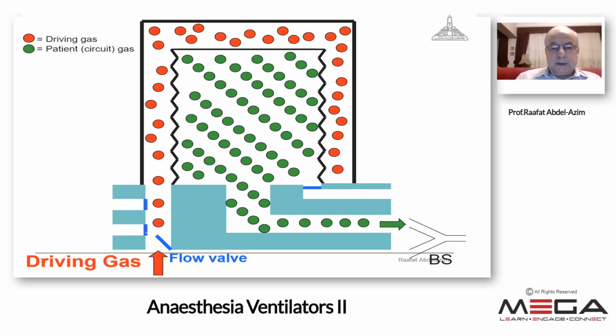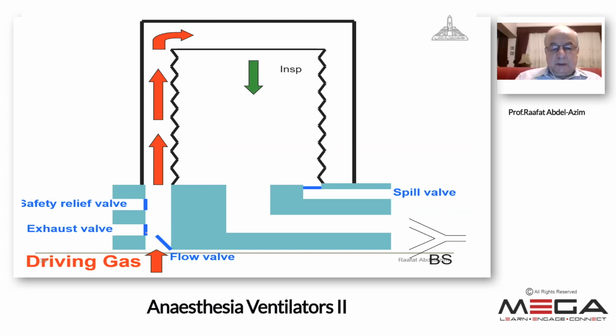As we see, we start ventilation. Flow is the driving gas coming into the chamber inside, and it will compress the bellows downward. The content of the bellows will come to the inspiratory limb and into the patient's lung. Only the flow valve is open and the other valves are closed.